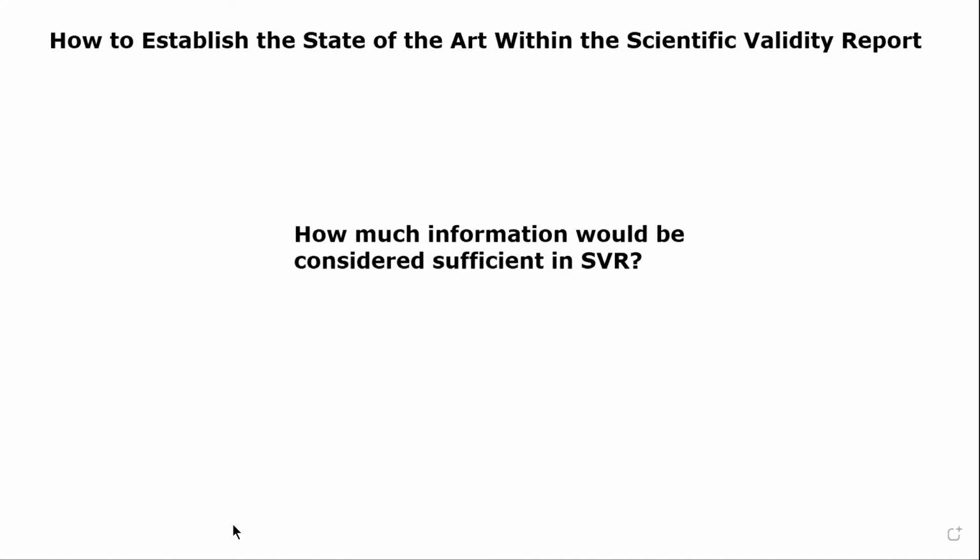One thing that I'd like to finish with is that the notified bodies will take reason and justification. In other words, if you well document in your reports, SVR, the PER itself, that you looked everywhere, that you did these things, this is down to your documentation of your methodology for searching for gray literature, as Sarah just described, or systematic literature review searching, or explanations or justification why there isn't very much data, and that you've looked under all these rocks and you've done your due diligence.